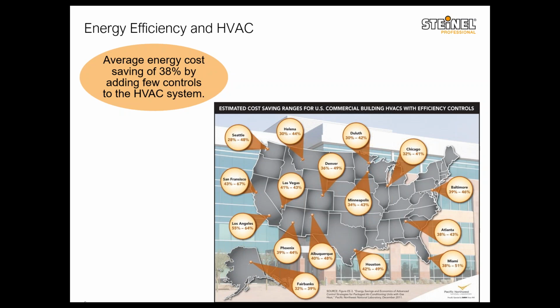So based on their study, average energy cost saving of 38% by adding few controls to the HVAC system. So imagine how much you can save by just doing a little upgrade on the occupancy sensor that the energy code requires you to put in anyway. You just add a little function to it, set it up, connect it to the HVAC system, and I'm not saying you will get a 38% just by adding the occupancy-based control. We will get to that as well, but it would be one of those measures that can easily help you have some energy savings.